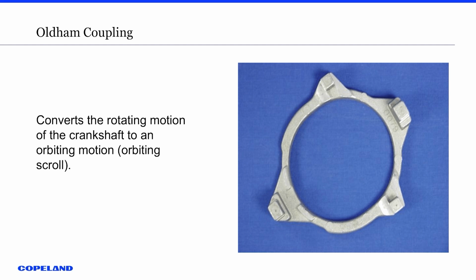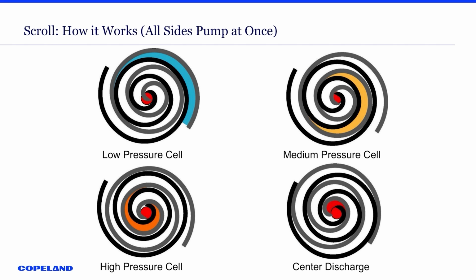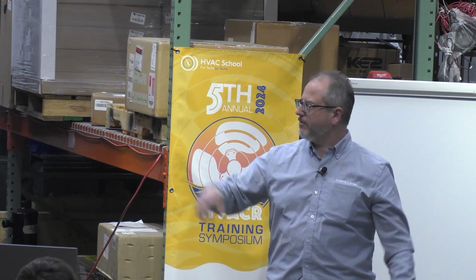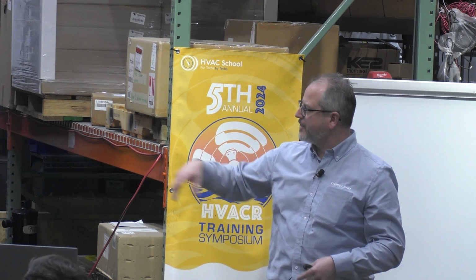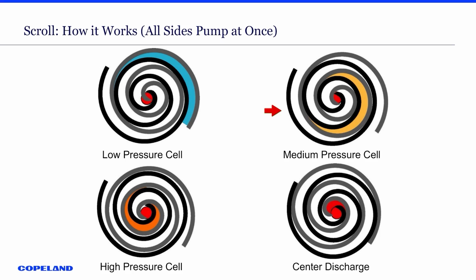So there's not much to it. When you see the scroll work, when it's moving, it takes about 3 rotations for that gas to go from the low pressure side on the left side, on the top, to the center where it discharges out. So it brings it on the outside, and it's constantly doing it. As we're bringing gas in, we're discharging it. We have gas in the medium pressure cell, we have gas in the high pressure. It's continually squeezing that refrigerant through.